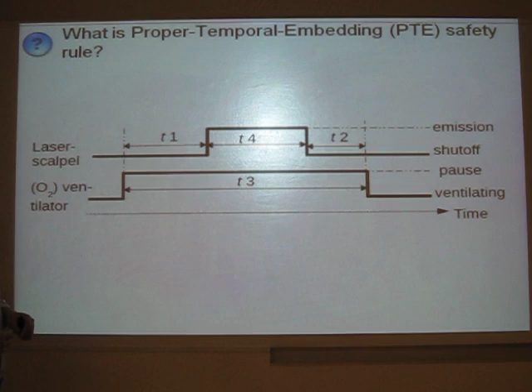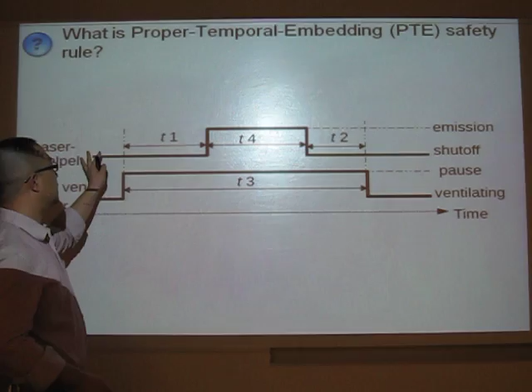So what is proper temporal embedding, or PTE safety rules? I'll use an example and you will immediately understand it. This example is about laser tracheotomy surgery, a medical CPS. In the laser tracheotomy surgery, the surgeon uses a laser scalpel to cut open the trachea of the patient. On the other hand, the patient is under anesthesia. Therefore, we have to use a ventilator to provide the oxygen to the patient. And you can imagine if the ventilator is ventilating oxygen through the trachea and you shoot the laser, then the laser will trigger fire, causing accidents. Therefore, in laser tracheotomy, the interval that the laser scalpel shoots laser must be properly embedded by the time interval that the ventilator pauses.